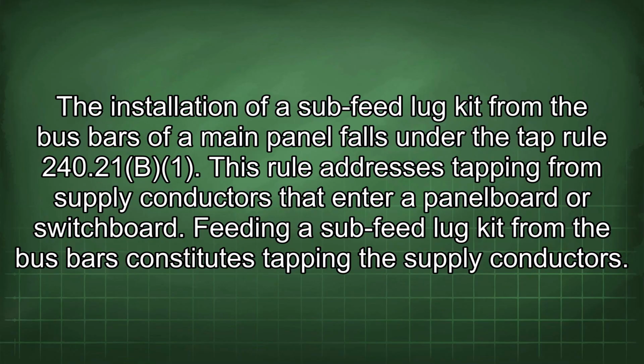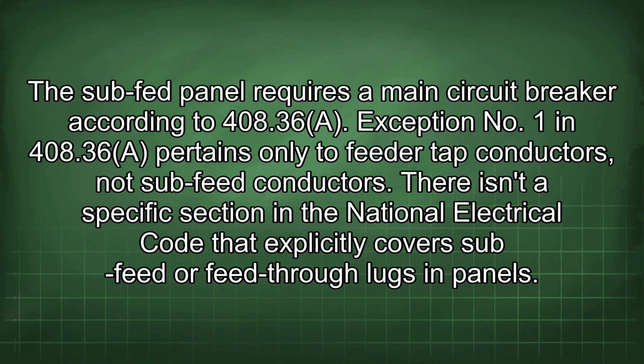The installation of a sub-feed lug kit from the bus bars of a main panel falls under the TAP Rule 240.21(b). This rule addresses tapping from supply conductors that enter a panel board or switchboard. Feeding a sub-feed lug kit from the bus bars constitutes tapping the supply conductors. The sub-fed panel requires a main circuit breaker according to 408.36(a).